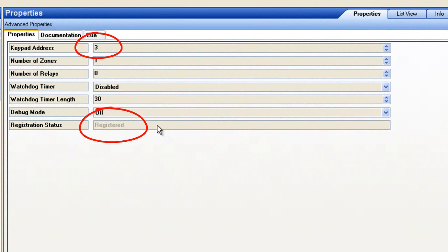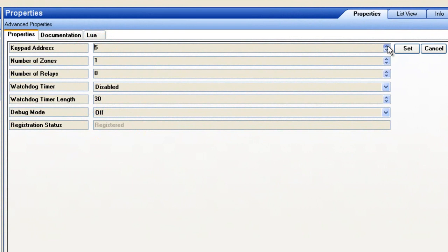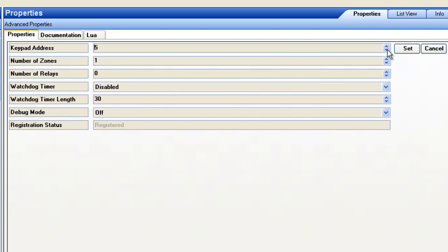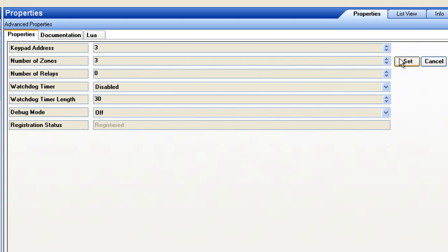From here, you can modify any of the HHIM settings. The keypad address can now be assigned to the appropriate address required by the Security Panel. Now change the number of zones. Input the highest number of zones you would like to monitor, even if they are not all used.